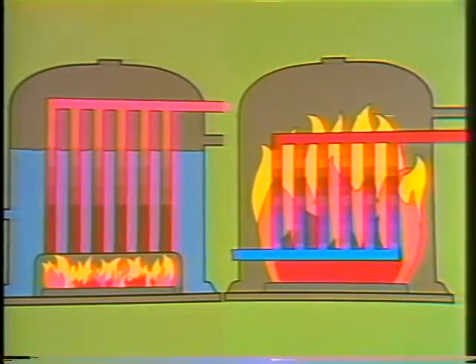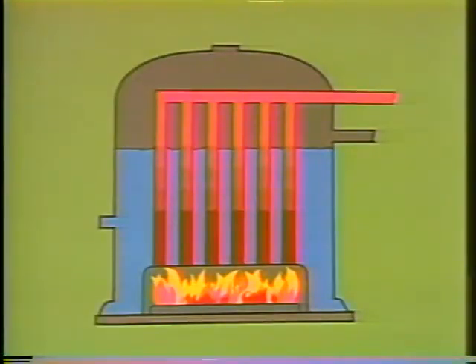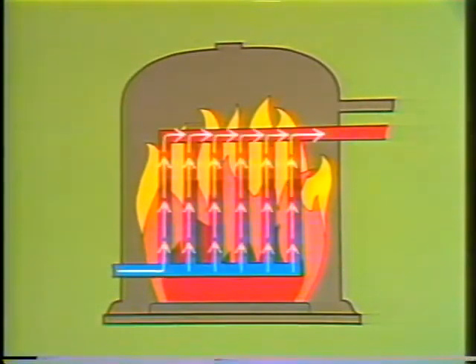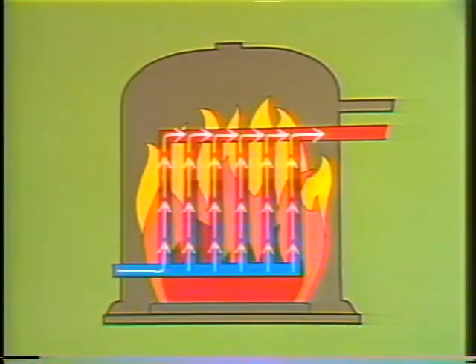As these names indicate, there's a difference in what the two types of boilers have in their tubes, as well as in the unit's basic construction. Fire tube boilers, which are sometimes used for heating, pass hot gases from combustion through tubes surrounded by water. The hot gases heat the water around the tubes, producing steam. In water tube boilers, the locations of water and gases are reversed — water flows through the tubes, and hot gases surrounding the tubes heat the water to produce steam.